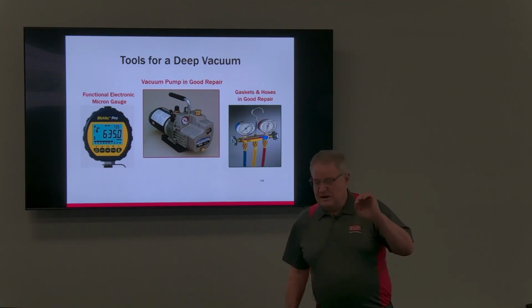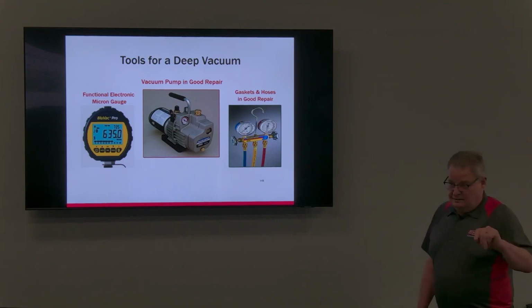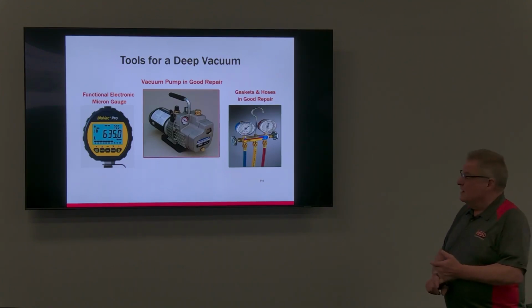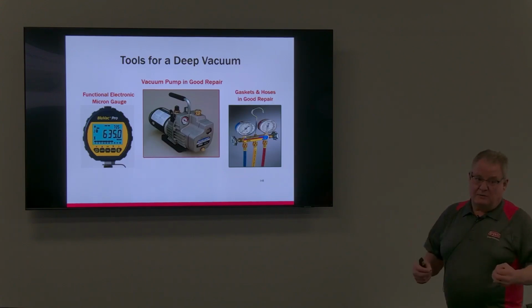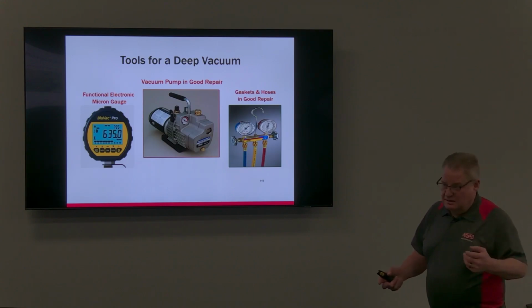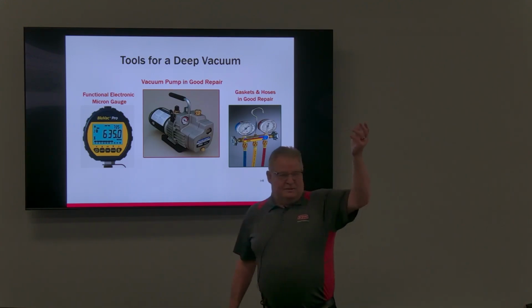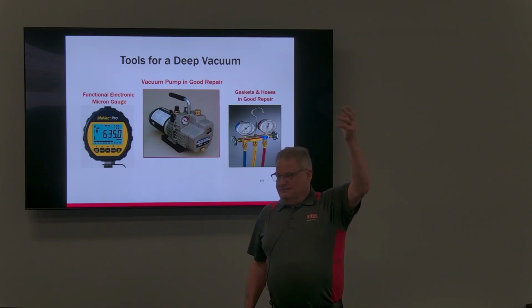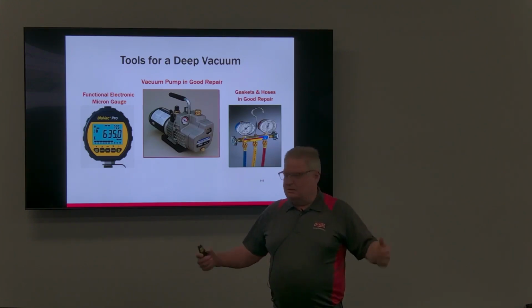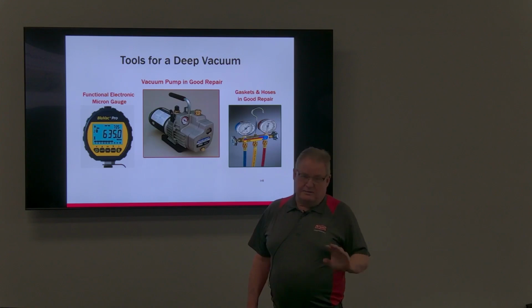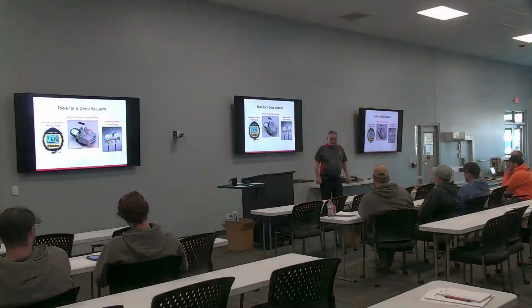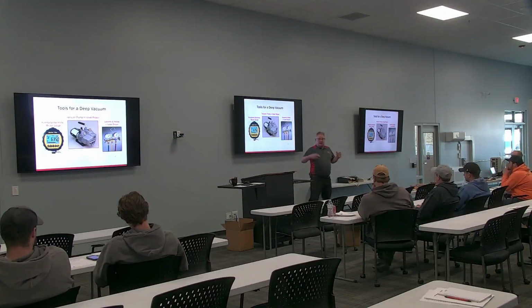So something we want to be careful with POE is that it's dry, okay? We keep it dry, we keep the system dry. It is possible to get POE so wet we can't dry it out. Okay, it'll actually break down to mild acid and alcohol. If you get called out on a system that's been sitting, and sometime this winter something got shot and blew a hole in the condenser and you lost all the charge, you might want to do an acid test on that oil. Okay, because if it's been open and exposed to moisture all winter, the vacuum pump won't get it out. Because if there's enough moisture, it'll actually just break the oil down to acid and alcohol. So just be aware of that.